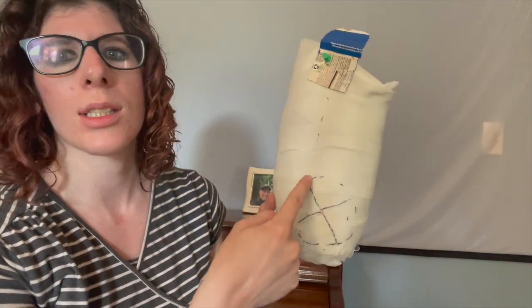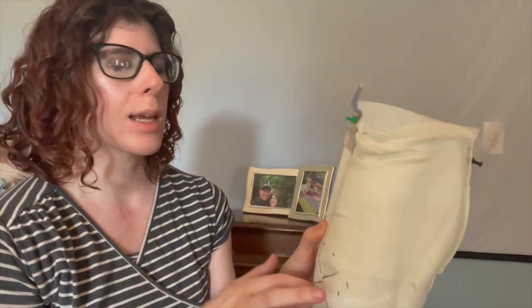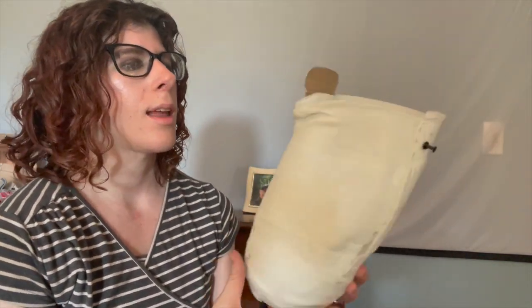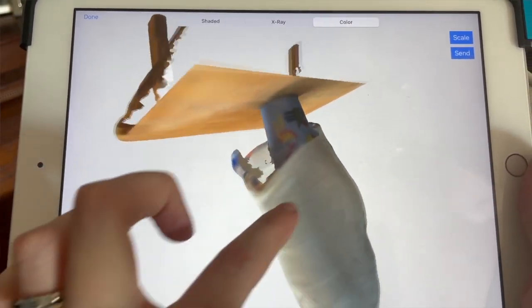Another common issue is space and non-contact at the distal medial area, so on the cast I'll cut an X pattern and just push that in to reduce that distal non-contact. Once those adjustments are made — the ischial seat built, the alignment line marked — we go ahead and scan. I'm going to instruct them to smooth out this lateral channel, smooth out this area, and follow the cast for trim lines. Here's basically what the transfemoral scan looks like, and in the next video in this series we'll be fitting the check socket.